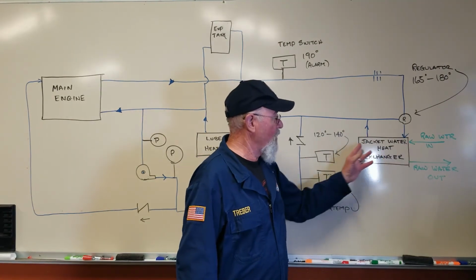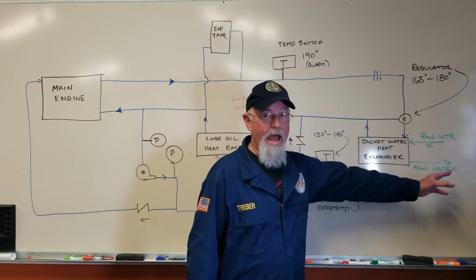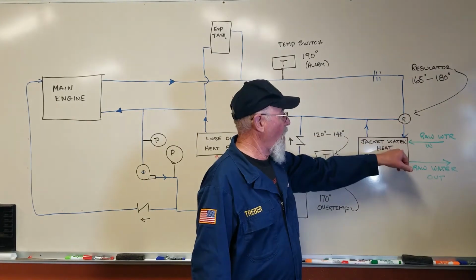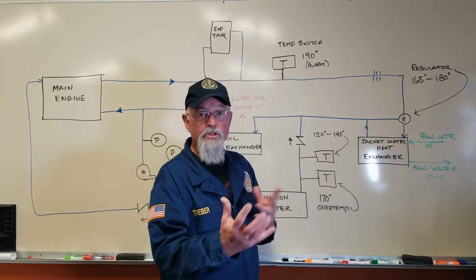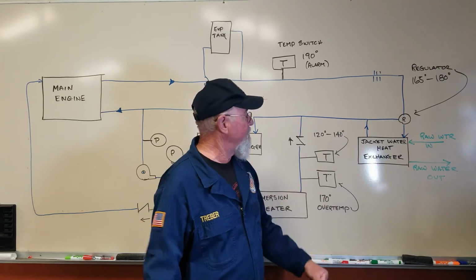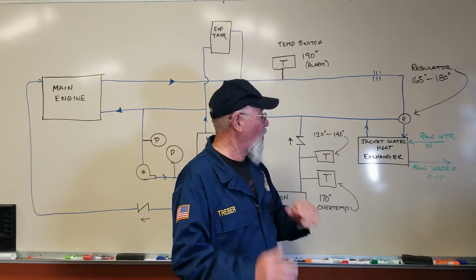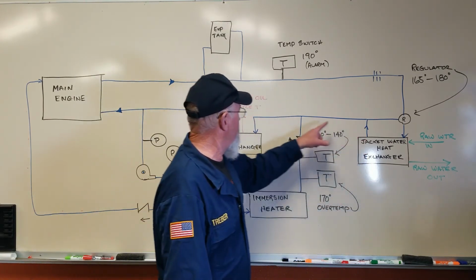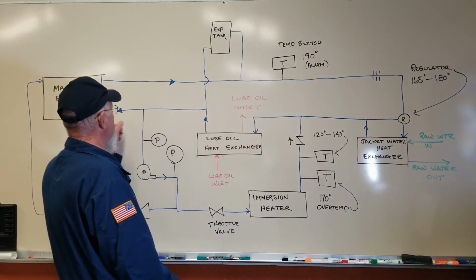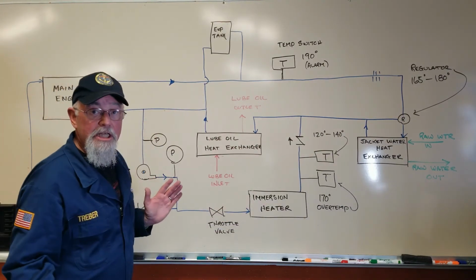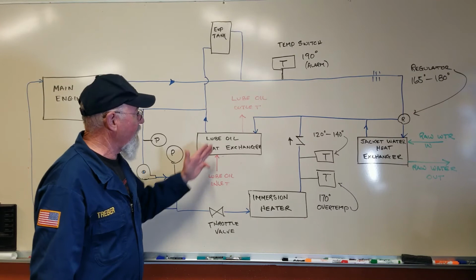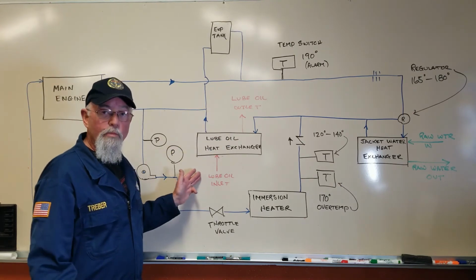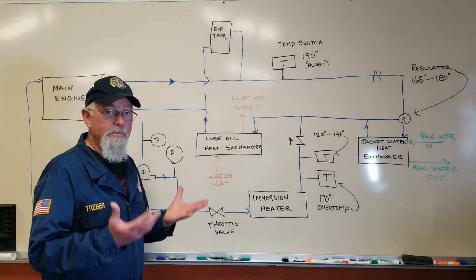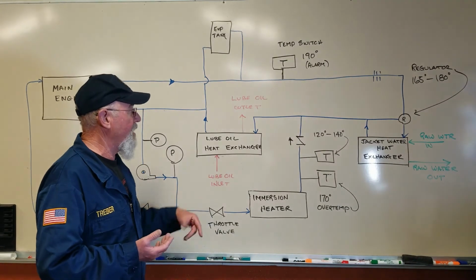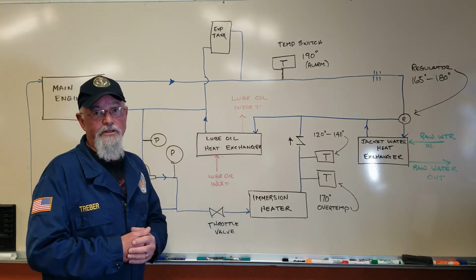So seawater's going through the tubes, coming in, going out, going overboard. The jacket water's going over the outside, and if you have a temperature differential, you're exchanging heat. So heat always goes from hot to cold. It comes out of the jacket water heat exchanger, goes back through here, and that's basically it in a nutshell. I didn't put a whole lot of illustration into the lube oil part of it, because it's just that simple: a pump circulating oil from the sump through the heat exchanger back to the sump.